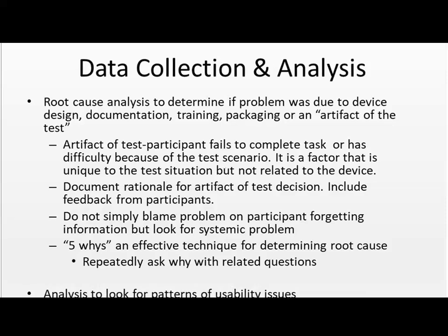Now let's talk a bit about root cause analysis. You want to find out if the problem is due to the device design, to the documentation, to the training, to the packaging, or if there's a, quote, artifact of the test. An artifact of the test is when a participant fails to complete a task or has difficulty because of the test scenario.